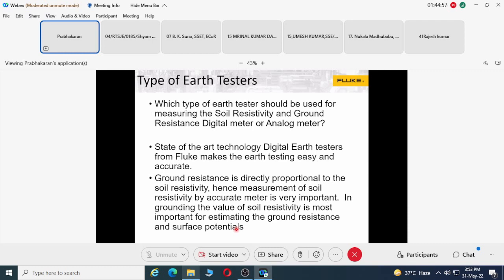I'm just touching upon these things because otherwise we may take a lot of time. Similarly, what kind of testers should you use for measuring soil resistivity? Earthing is actually designed based on the soil resistivity, the resistance of the soil present at that facility. You have to find that resistivity, and then decide what kind of earthing you need, whether pipe earthing, mesh earthing, or plate earthing.